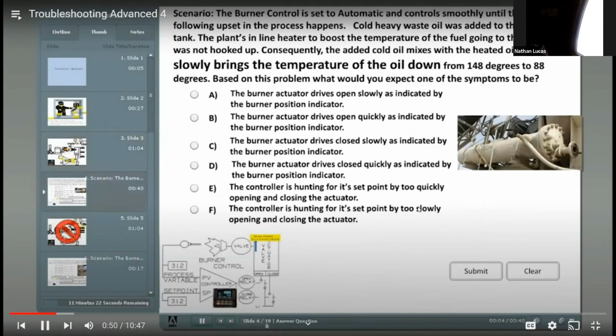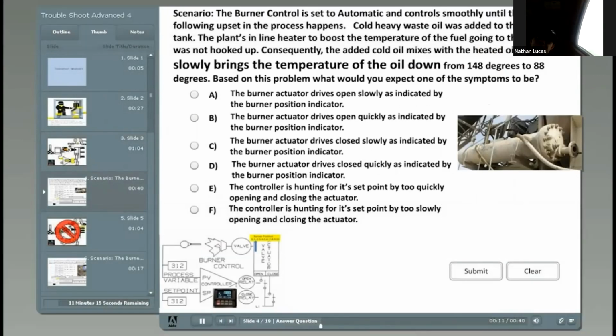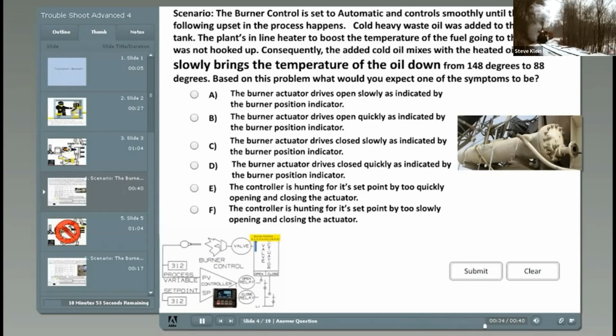Scenario: the burner control is set to automatic and controls smoothly until the following upset in the process happens. Cold, heavy waste oil was added to the fuel tank. The plant's inline heater to boost the temperature of the fuel going to the burner was not hooked up. Consequently, the added cold oil mixes with the heated oil and slowly brings the temperature of the oil down from 148 degrees to 88 degrees. Based on this problem, what would you expect one of the symptoms to be?